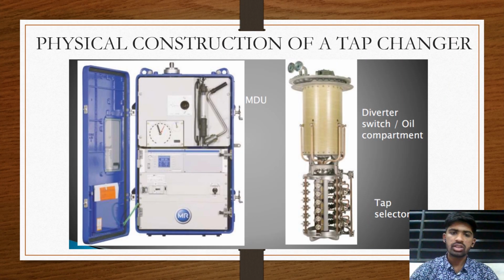Here we can see the physical construction of a tap changer. On the right side, we see a picture where the diverter switch, or the oil compartment, is present above the tap selector. On the left side, we have something called an MDU. This MDU is the motor drive unit. This unit has a motor drive and other necessary controls. The motor charges the spring to rapidly perform the switching process. Power is transferred via shaft and gear mechanisms.